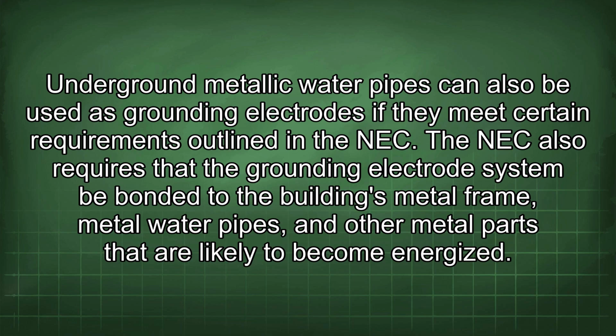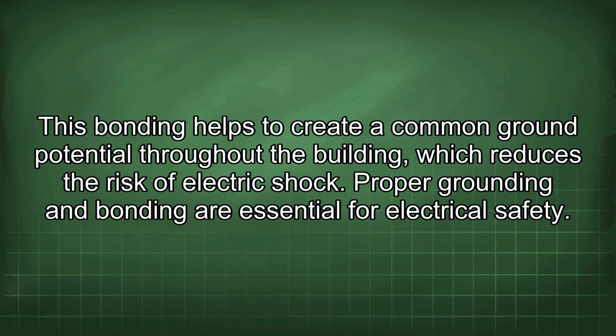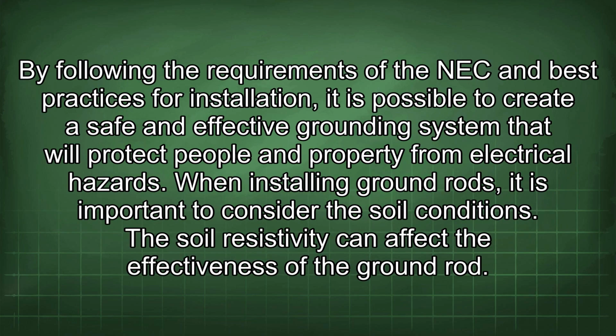in the NEC. The NEC also requires that the grounding electrode system be bonded to the building's metal frame, metal water pipes, and other metal parts that are likely to become energized. This bonding helps to create a common ground potential throughout the building, which reduces the risk of electric shock. Proper grounding and bonding are essential for electrical safety. By following the requirements of the NEC and best practices for installation, it is possible to create a safe and effective grounding system that will protect people and property from electrical hazards.